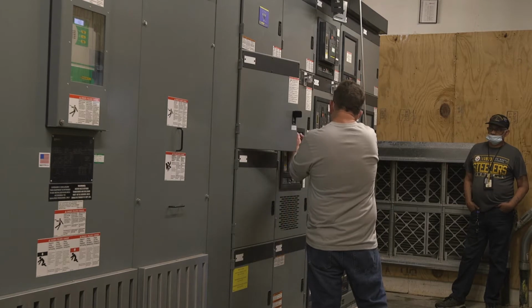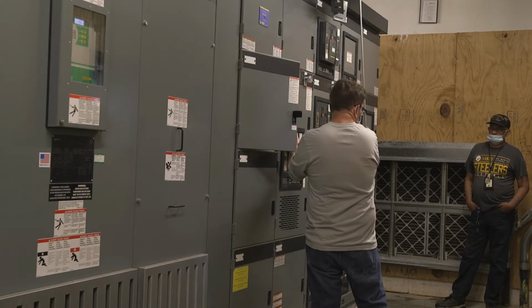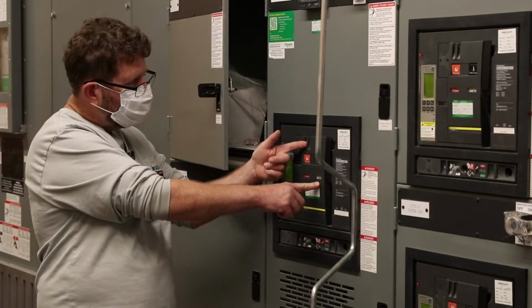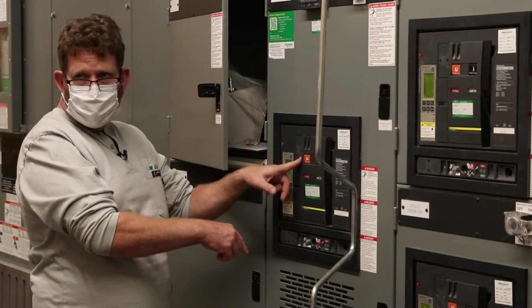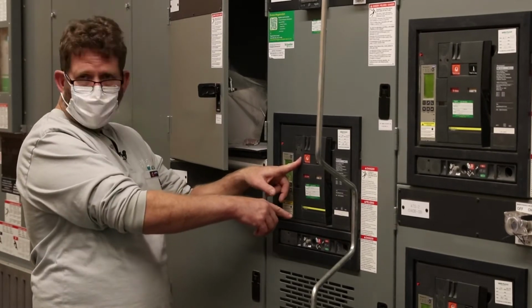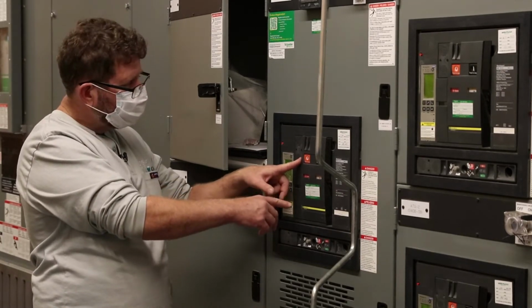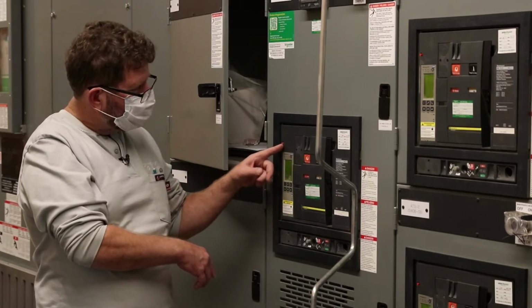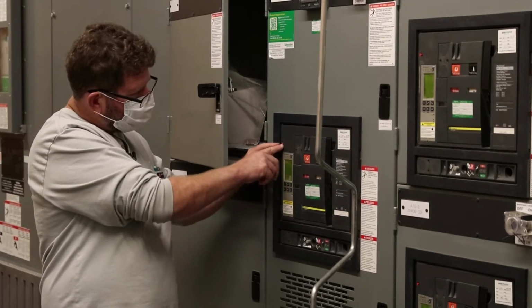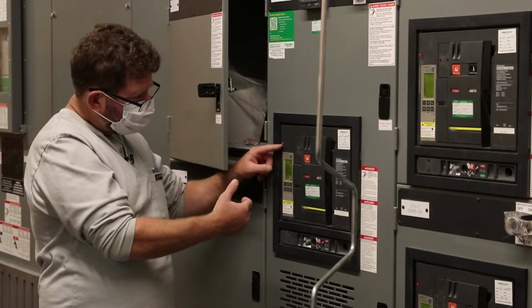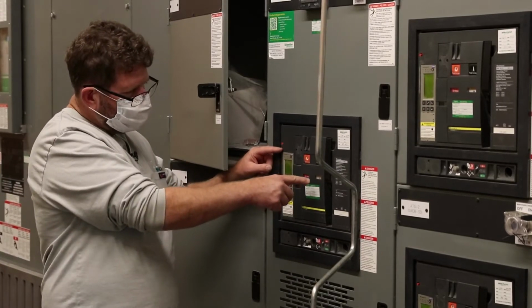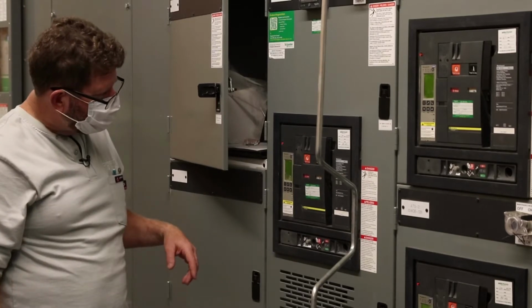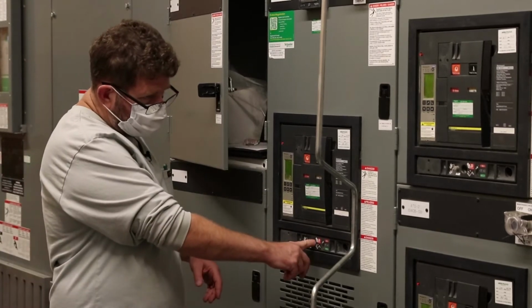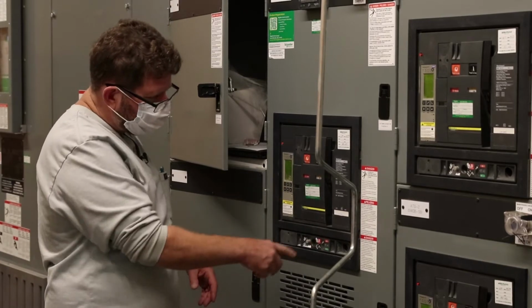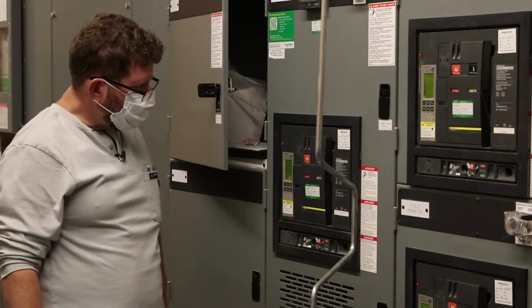If the breaker was open and you had the padlock attachment pulled out and the springs were charged, you'd see charge not okay. If you're holding the open button and the springs are charged, you'll see charge not okay. If the breaker is tripped, when the trip unit trips the breaker, this red button pops out. If the red button's popped out, it's going to say charge not okay. If your racking handle is installed, the breaker's interlocked off and it's going to say charge not okay.